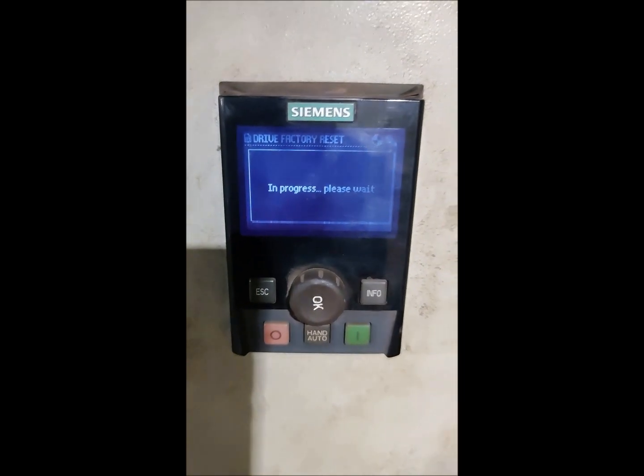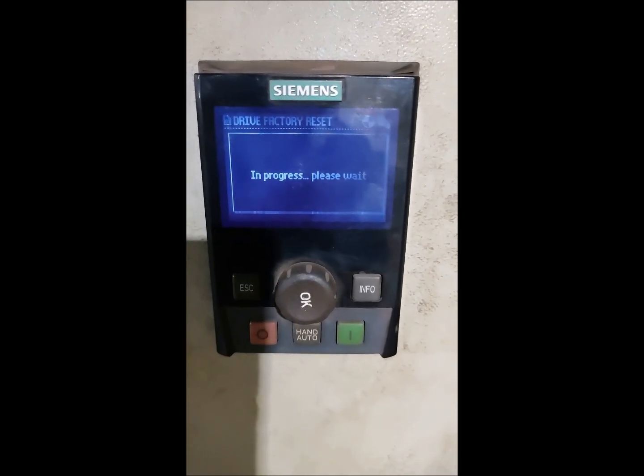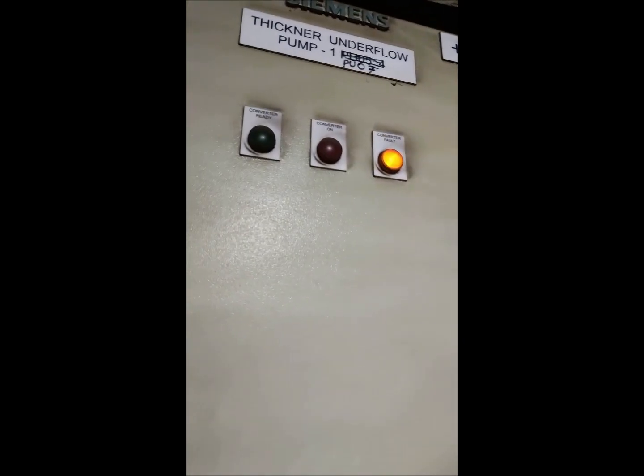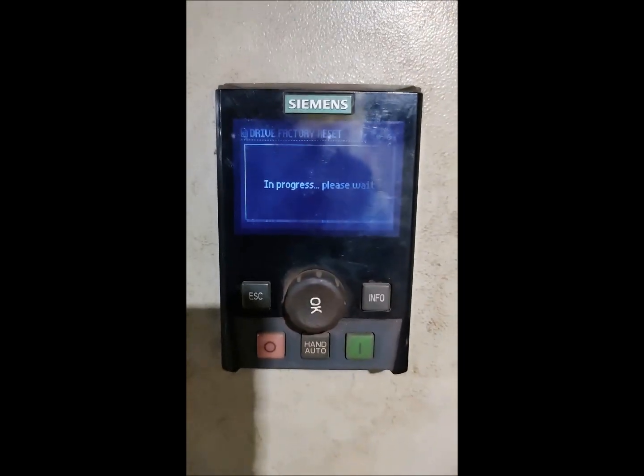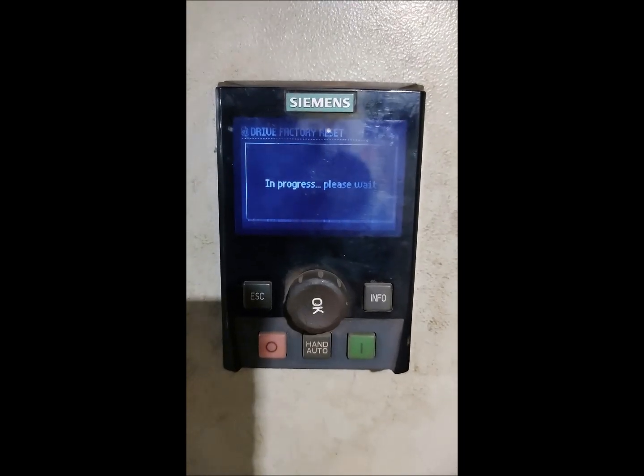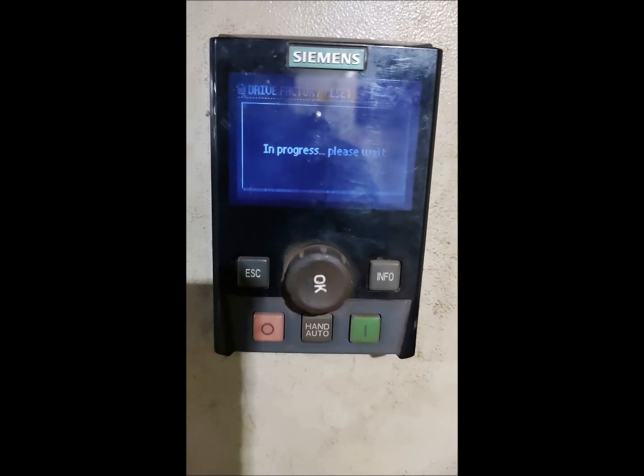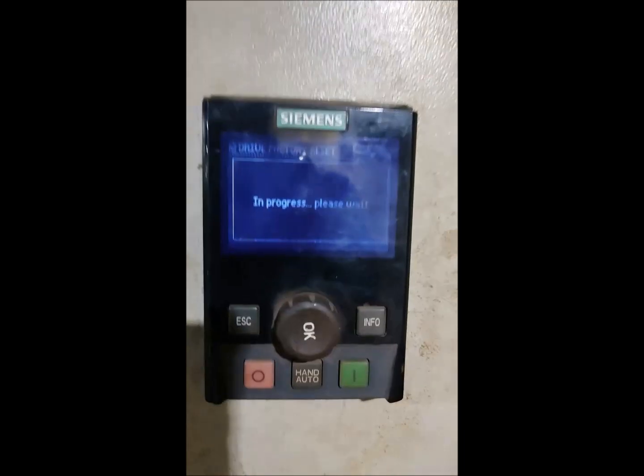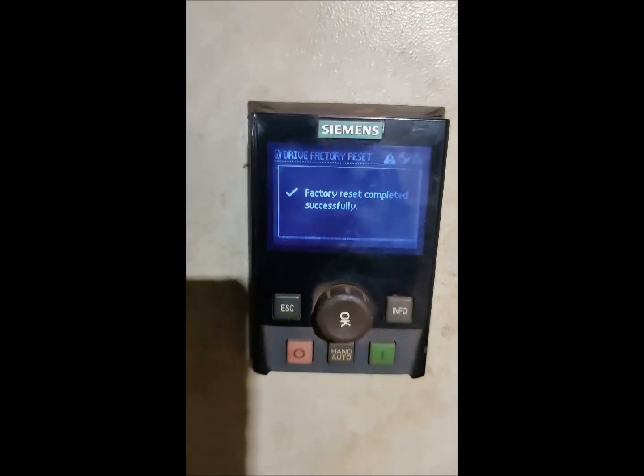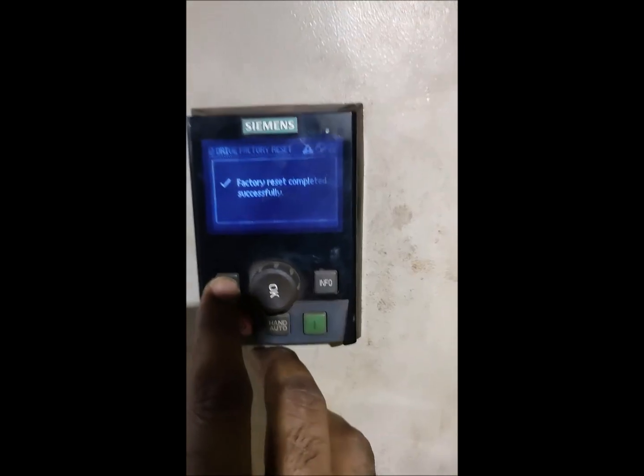In progress, please wait. So we have to wait around 30 to 40 seconds and the drive status will be fault, and the orange indication you can see on the panel. Once the factory reset is done, the actual value of power that will come to the drive - that we will check. So factory reset completed successfully, and still the drive will show in faulty condition because we have to do the programming next.